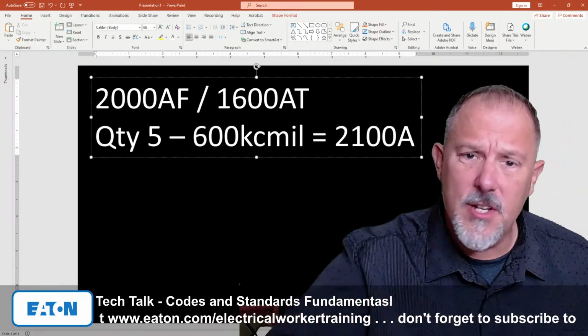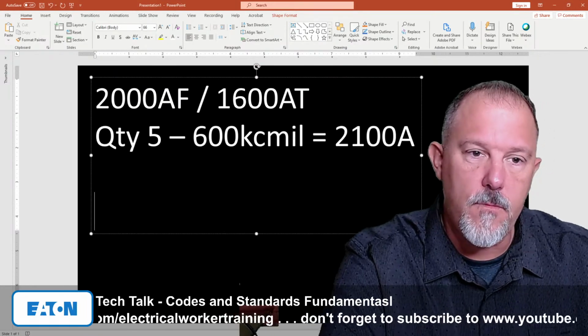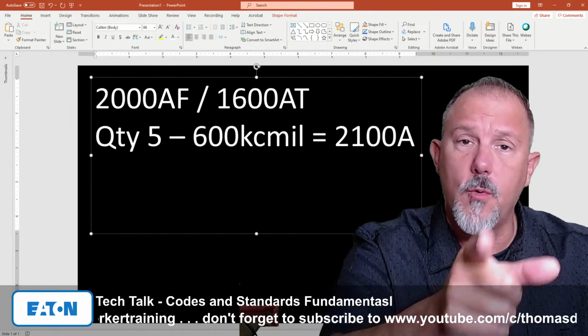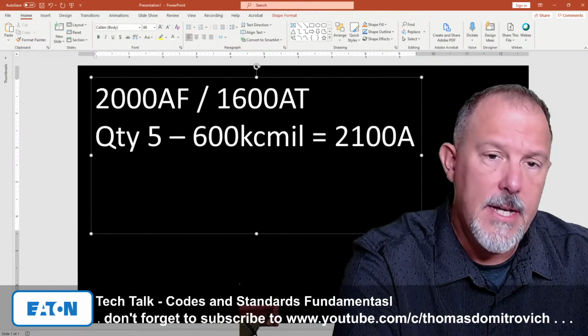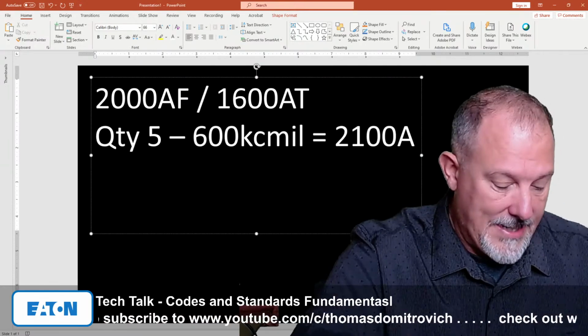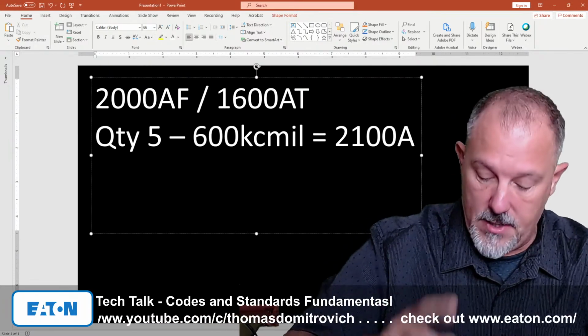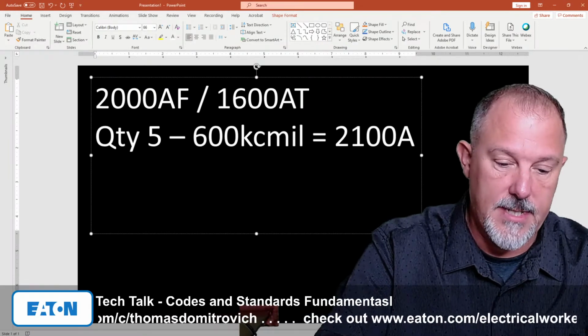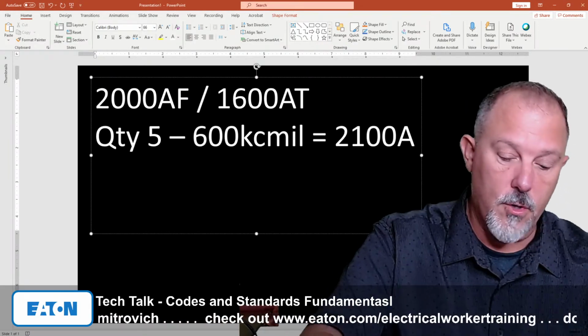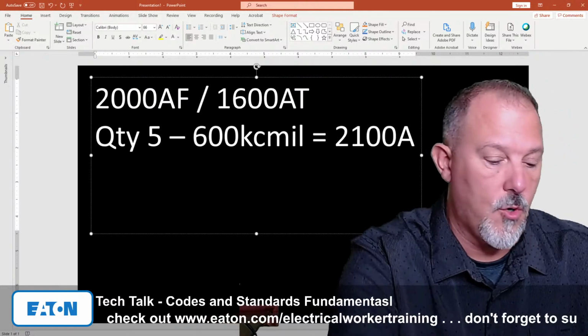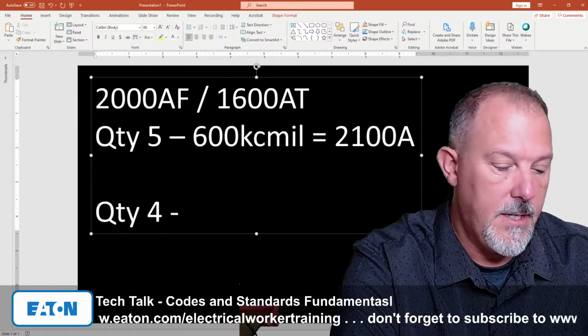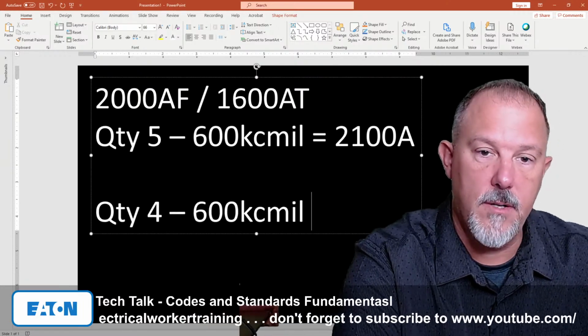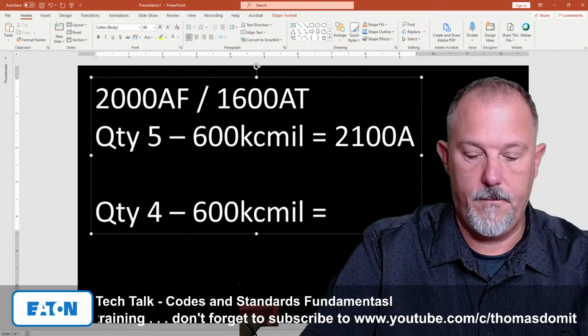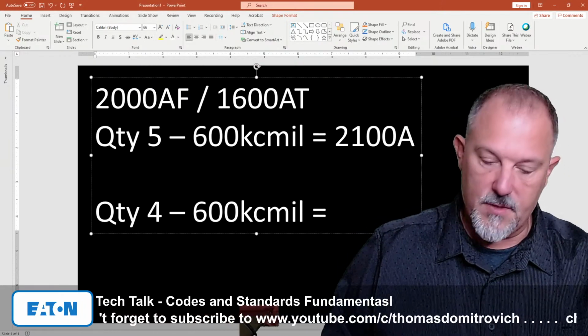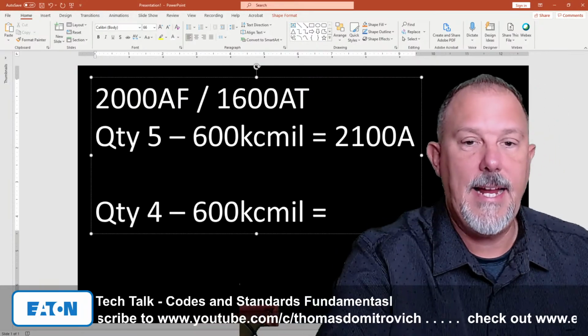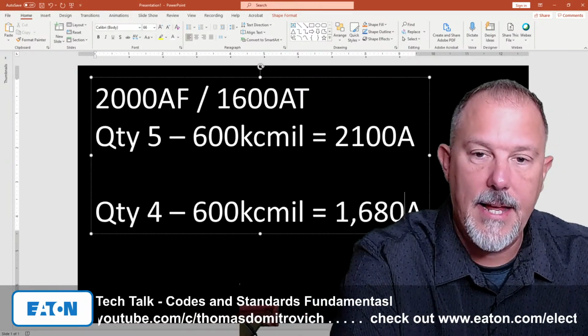So here was the question, and I'm going to lay this out. What this gentleman asked me during our last Friday call, he says, can I use, so what's 1600 amps? Let's just use 600 kcmil. So if I had 1600 amps, 1600 divided by 420 is 3.8. So quantity 4, 600 kcmil is equal to 4 times 420, which is 1680, 1,680 amps.